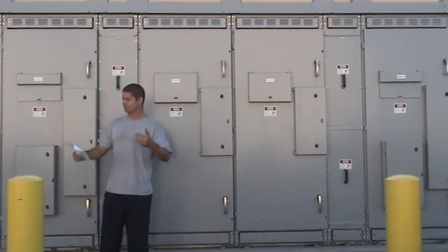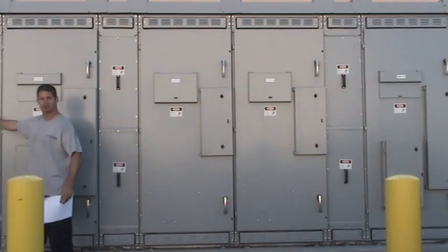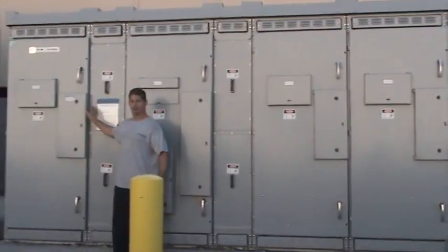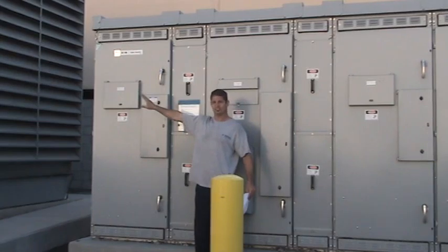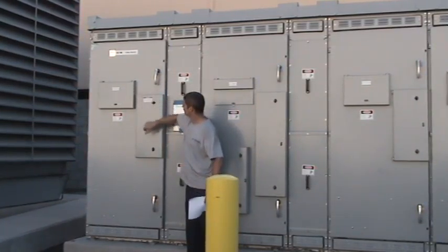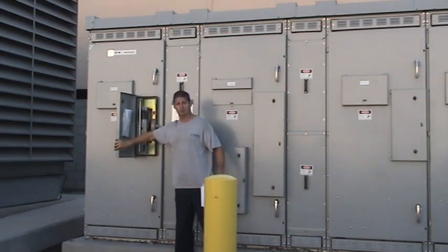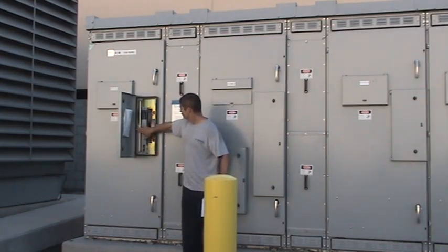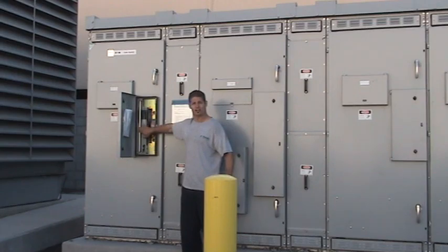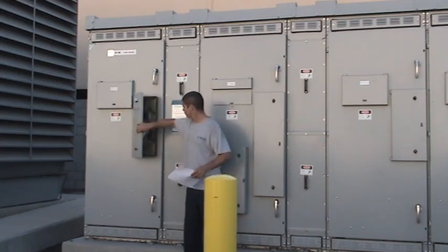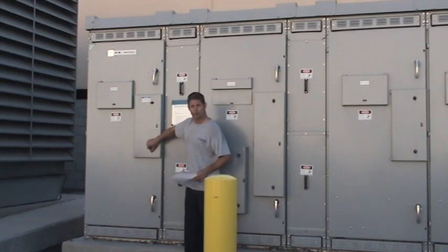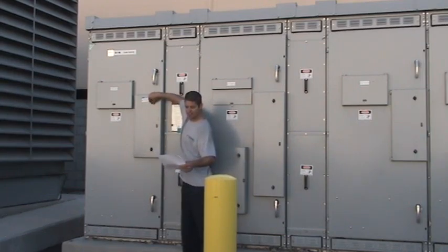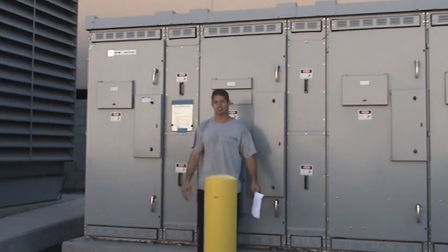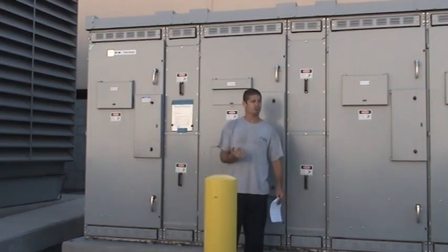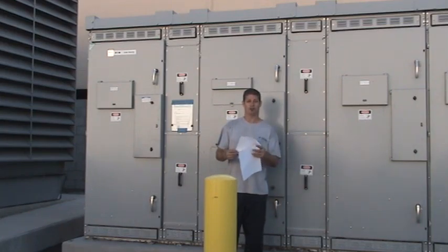So you've got the 2 on each side, and then the other manual switch right here would be the generator. This is the manual switch that leads to the generator right here. It's labeled from standby generator, and it has the same application. It's just a manual switch that's in a closed position at all times, right? So in the normal process, which is in auto, the functionality is all based on the sequence of operations that was given to us in the specifications. That sequence of operations is page 2 of what you have here.